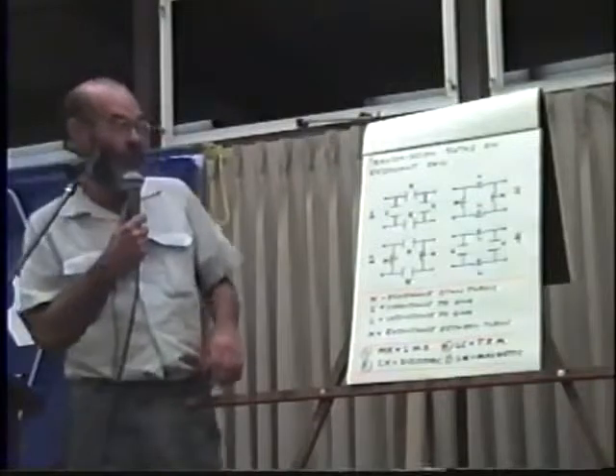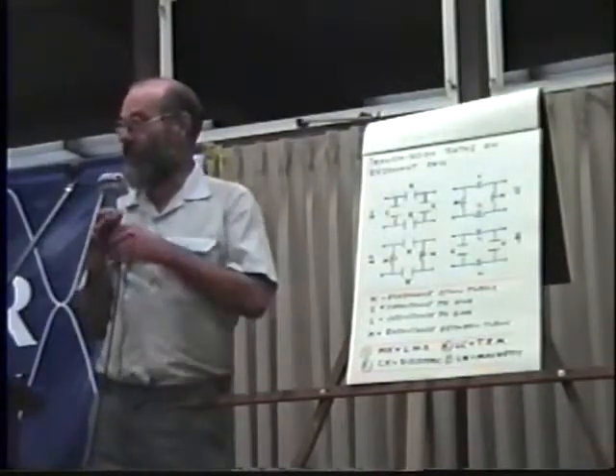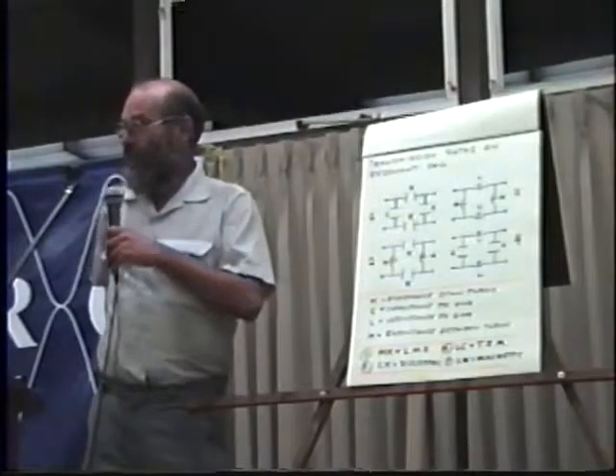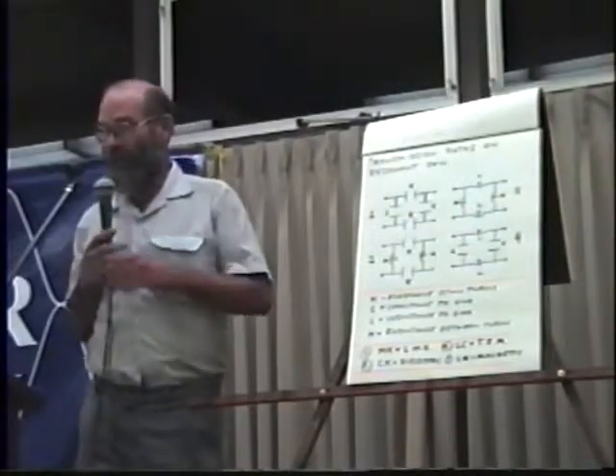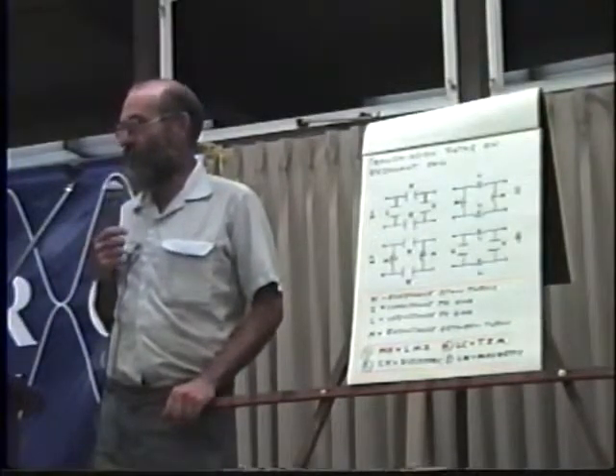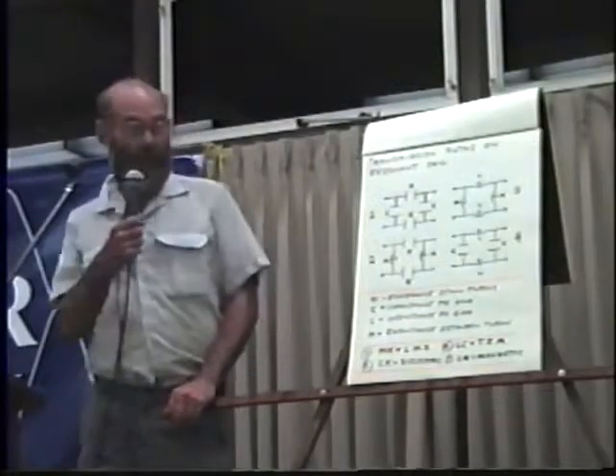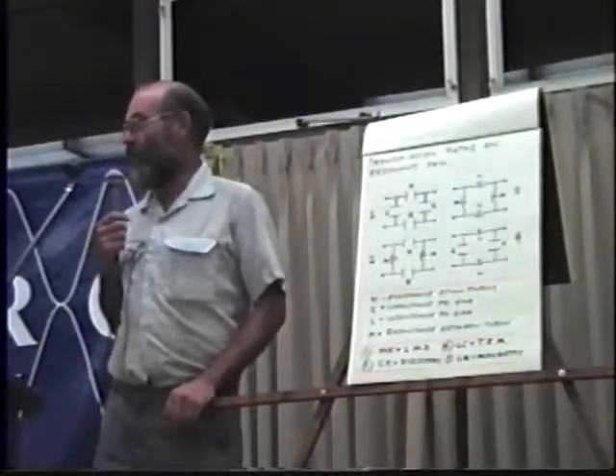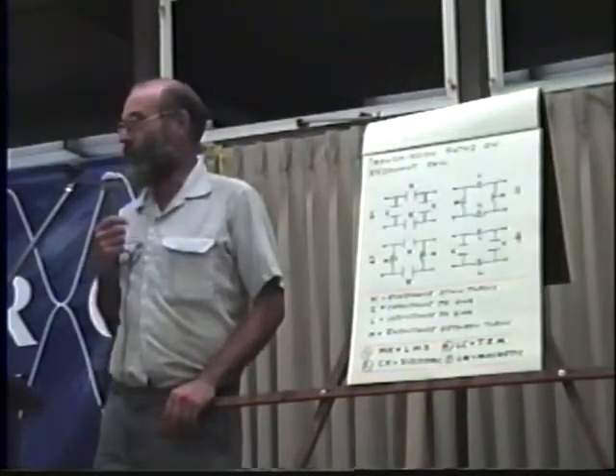This really led to a lot of confusion in the early attempts of the GE laboratories to ascertain why these complex waveforms they were experiencing in their substation transformers were causing them to explode for no unexplainable reason. The standing waves would build up and appear in the center of the windings and puncture the insulation, but yet from terminal to terminal there was no voltage difference.